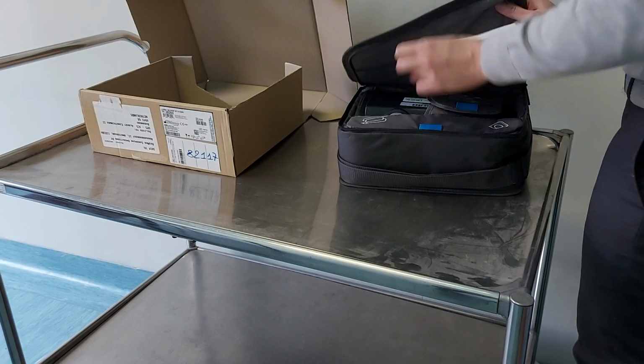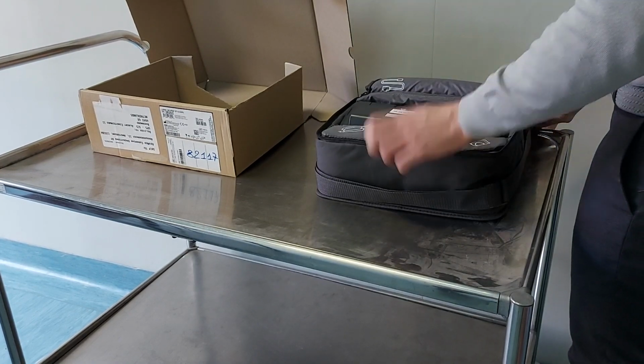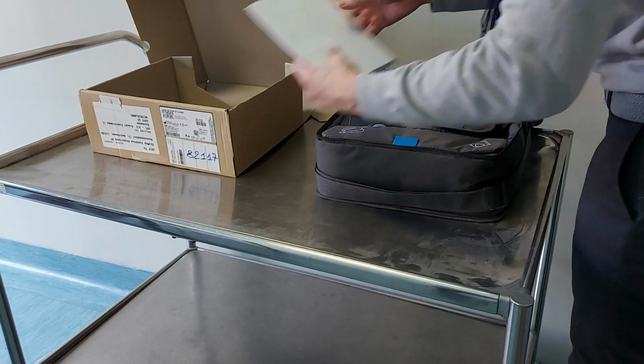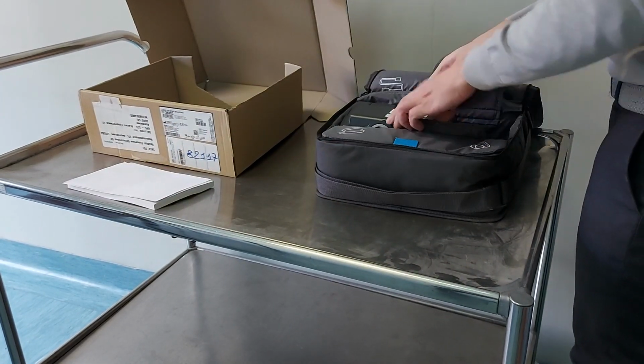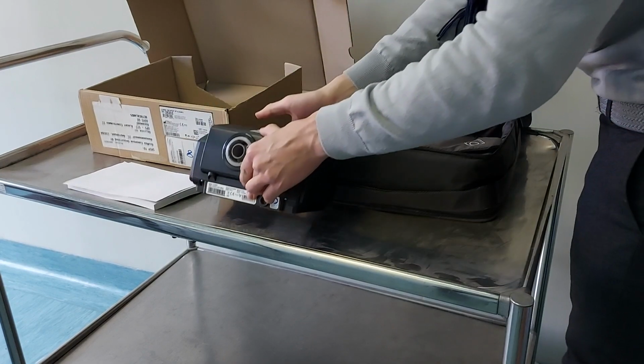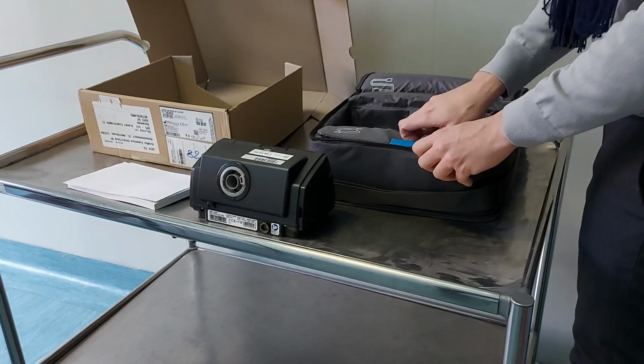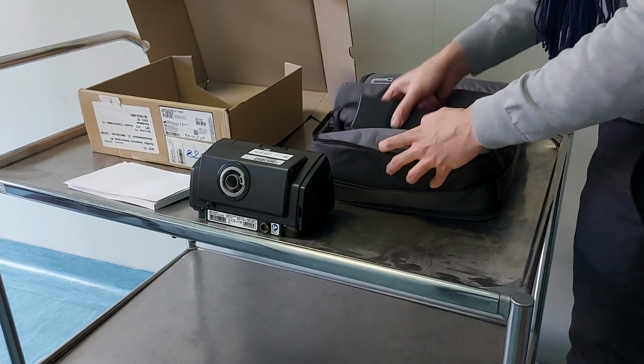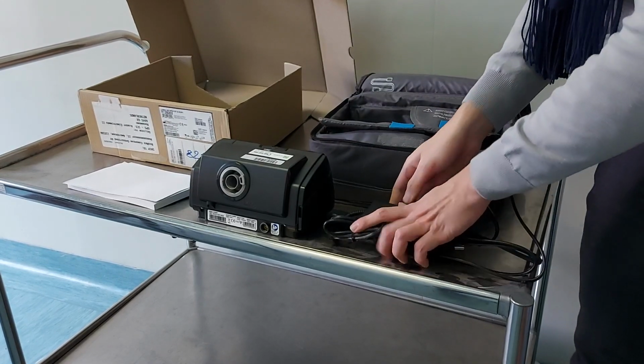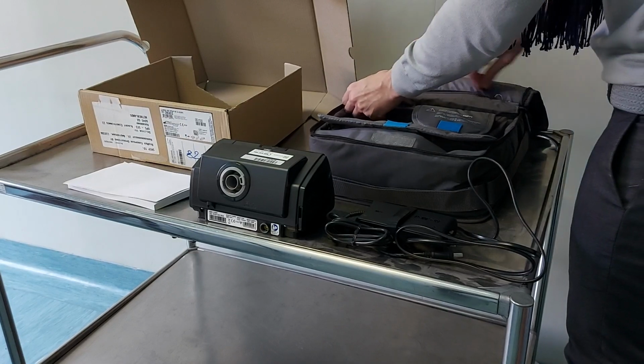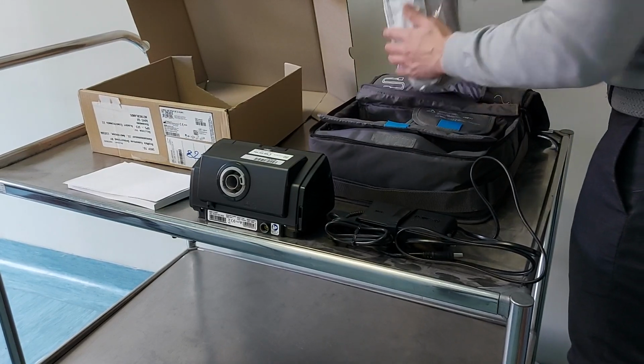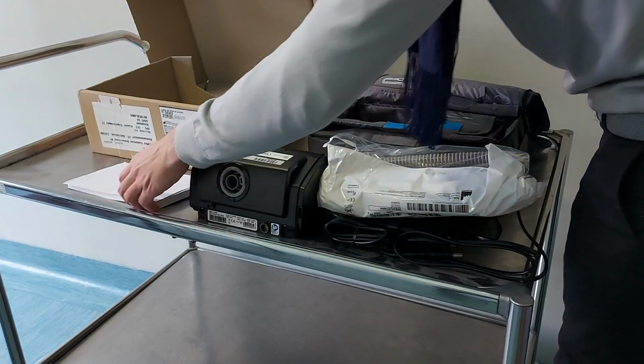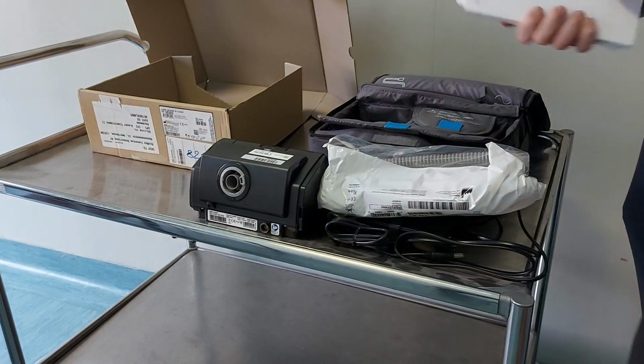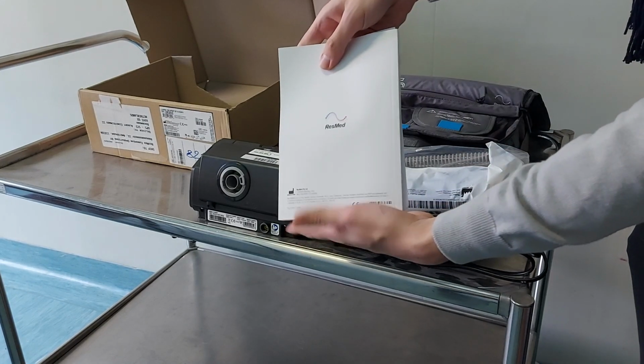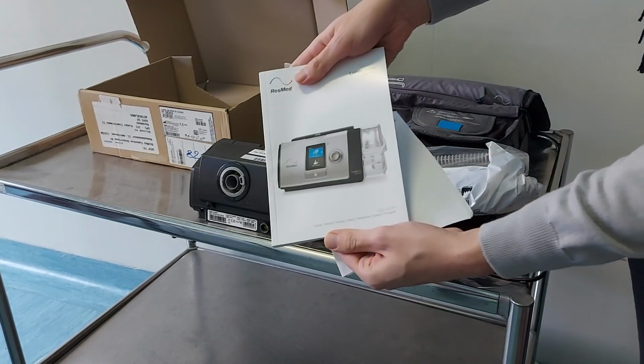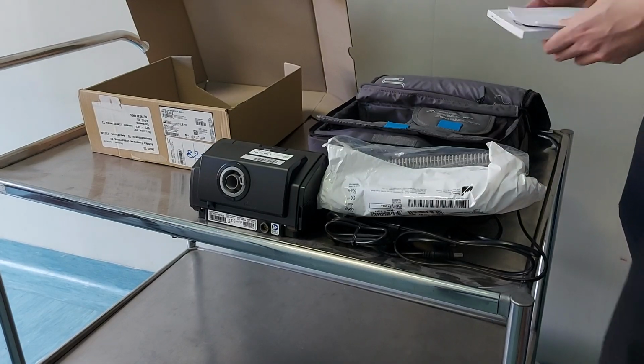Open up the box containing the CPAP or BiPAP carefully. Open up the other boxes from the order and check the contents against the packing slip and the purchase order. Note any discrepancies or any damage to the device or accessories that may have happened during shipping and report it right away. The vendor should be contacted directly or through your administrative process. Make sure both the user manual and the service manual are included in the box. Some vendors provide the manuals on CD or online. Verify that the documentation is accessible.